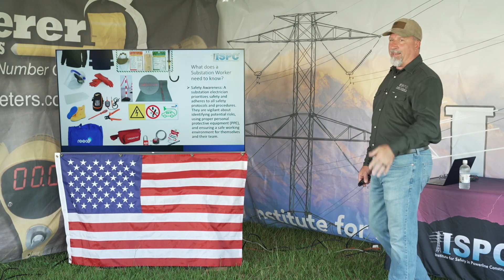There's equipment here, you can see PPE, tools, tags that we need to use to keep ourselves safe in the substation world. When we're working energized inside a control house on control equipment, we need to use insulated tools. When working with switchgear and metal-clad switchgear, and some things in our open air substations, we need to go above and beyond our normal FR PPE. So we have category 40, Cal 40 gear that we may have to put on because of the incident energy that could be there should something go wrong when switching on that equipment.